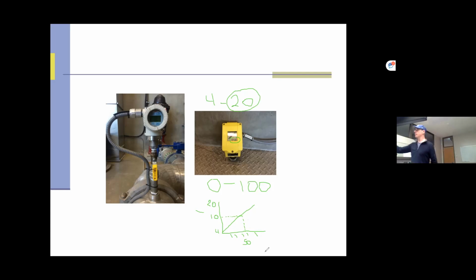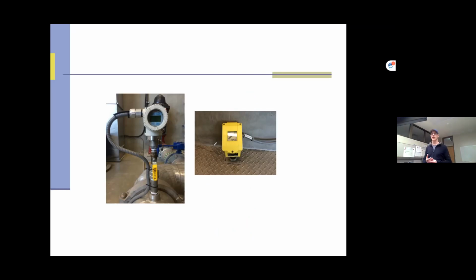Whether that's pressure or flow, and even in your lab, your chlorine analyzer in your hand there, right? When they put that color measurement in there and it reads it, all it's doing is measuring a voltage, a millivolt. At this color, it's going to send out this millivolt, and that's going to correspond to a chlorine residual that you understand when it spits out. So really, always keep that in mind. Instrumentation's fairly dumb. It's how you program it and scale it to make it work for you. All different types, like I said.